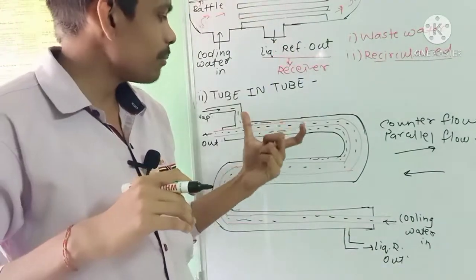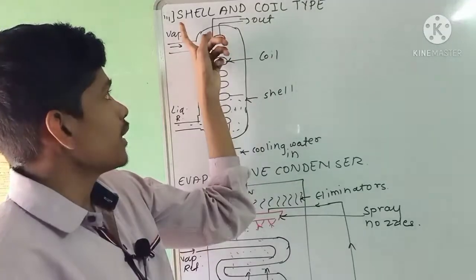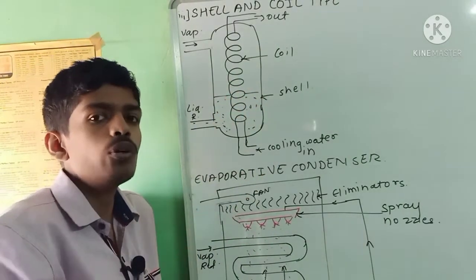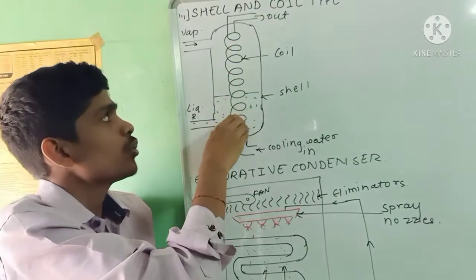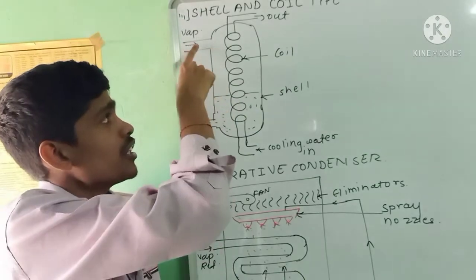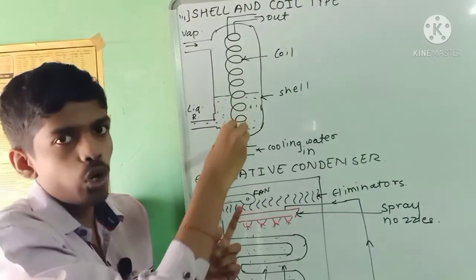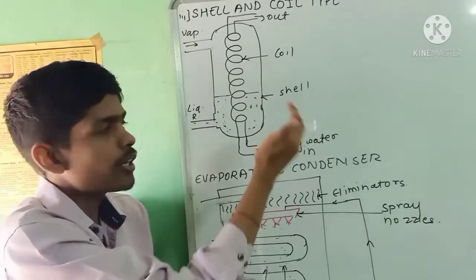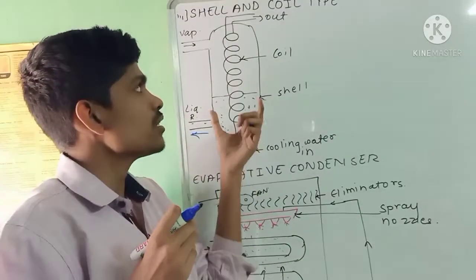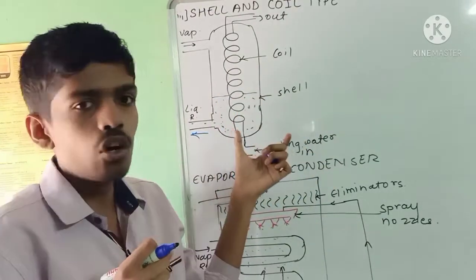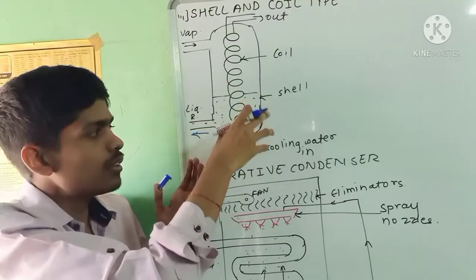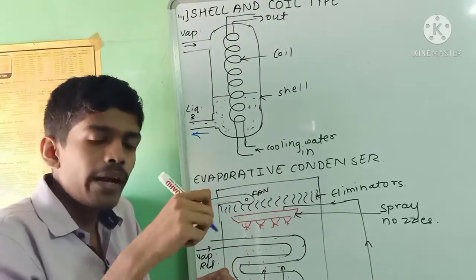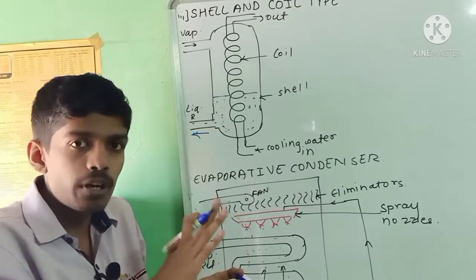The third type is the shell and coil type water-cooled condenser. It consists of a shell in which two or more coils are arranged. Cooling water flows through the coils, and vapor refrigerant enters from the top and flows over the coils. Heat transfer takes place, the vapor refrigerant gets cooled and converted into liquid refrigerant, which is sent to the receiver. These condensers can be vertical or horizontal. Since the coil is inside the shell, mechanical cleaning is not possible, but chemical cleaning can be done. The counter flow system is generally preferred here as it is more efficient.